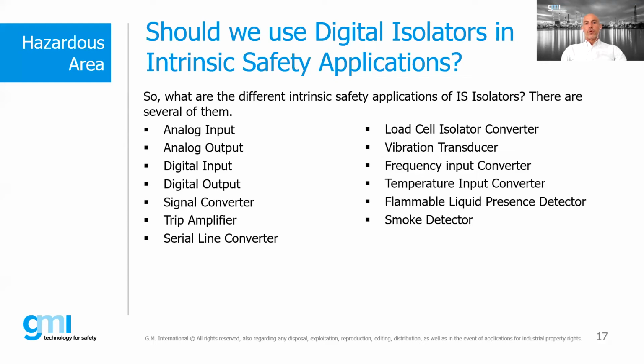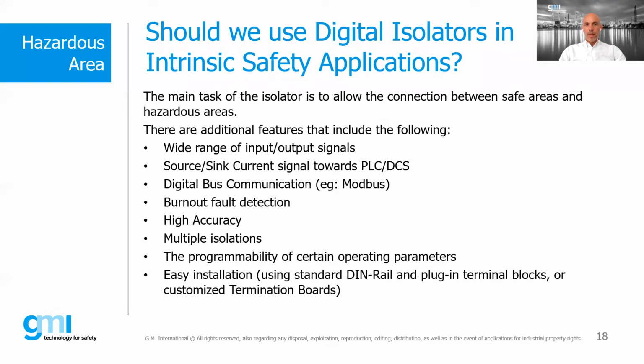Okay. And what are the different intrinsic safety applications for an IS isolator? You can have analog circuits, input and output. You can have digital, input and output. You can also use a signal converter, so you want to convert the signal from the hazardous area to the safe area. You can use a trip amplifier, a serial line converter. And you can have other very specific ones, like a load cell for weighing applications, vibration transducers, a frequency input converter, and temperature, flammable or smoke detectors. There are different applications for the digital isolators.